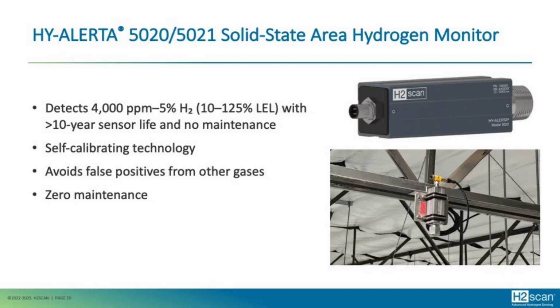So we have a couple of different models with this technology. We have the 5020, the 5021 series that are general location sensors, general to any hydrogen safety application. The sensor speaks Modbus RTU and it's very simple to operate. It is an analyzer, so it just gives you the data, and then you can connect this to your building management system to create your alarm set points.